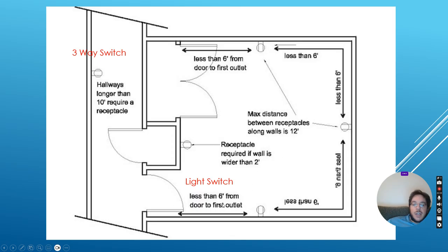Now, the other thing is, in Canada, we've got almost the same rule for spacing receptacles, except it's required for any wall that's 900 millimeters or longer, and receptacles must be within 1.8 meters of each other, but there's no rule about having one 6 feet from the door.